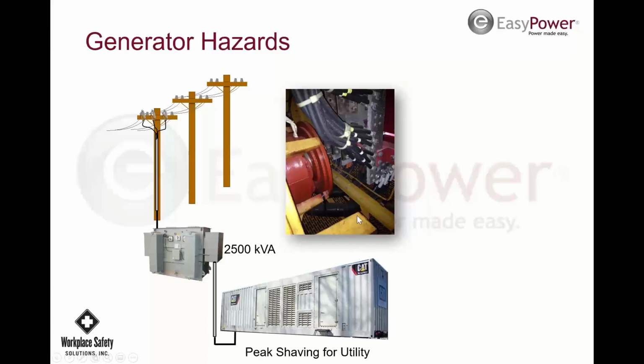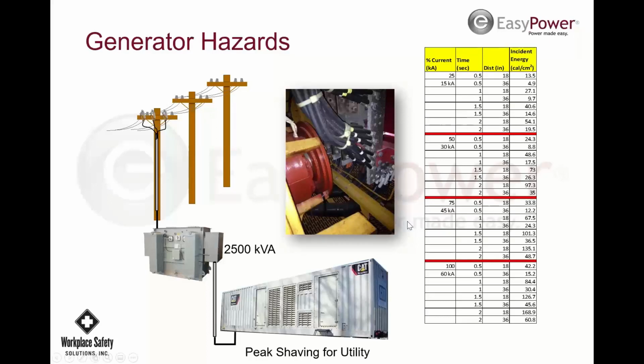So I started looking at this, and I said, well, what happens if you had a screwdriver that crossed against this? What would the arc flash level be with this transformer? So we got the transformer nameplate data, and we came up with this chart. So 75% of the full fault current is 45,000 amps. So I use that just as a tool. So at 18 inches, it's 101 calories. That's where he was sitting. Now, he was working with cotton clothing on. He would have just been nothing but toast. And I asked our engineer to give me what it is at 3 feet as well, and it's 36.